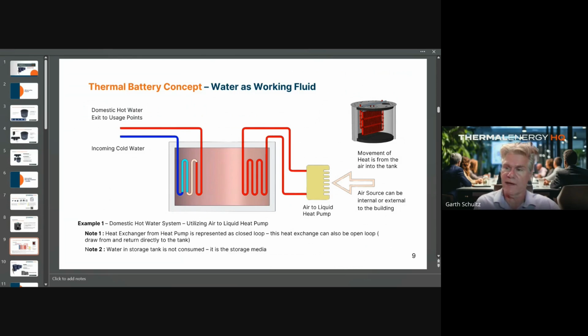And then on the lower end, if you want to use the tank as a buffering system for chilled water, you can go down to 40 degrees Fahrenheit as those processes demand. So it's universal in terms of what temperature you store at, and as the designer of the heat exchanger or of the system, you can spec where it is that my device can recapture and store, and what's the best utilization within my process.